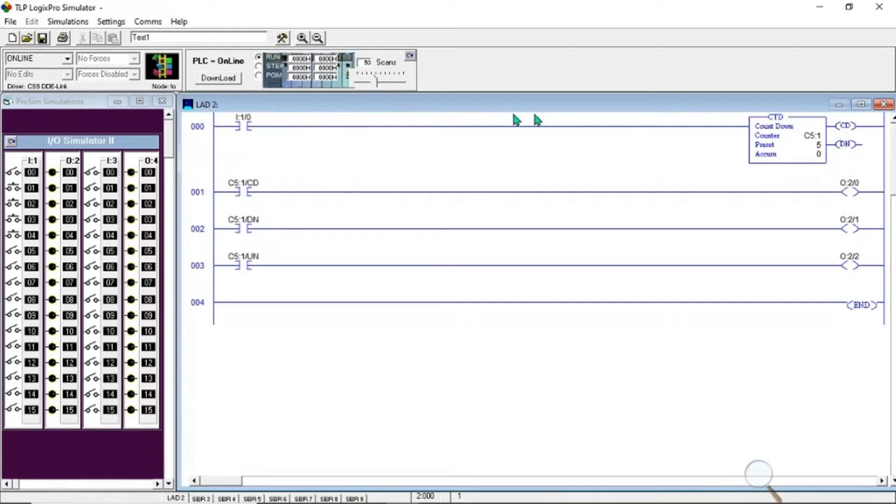The counters always go high whenever you have the transition from false to true in the input rung. From false to true, we have the signal making the counter true, and the countdown bit is now enabled, so it will turn on the output. You can see that the accumulator is now counting down, from 0 to -1, then -2, -3, -4, and so on.